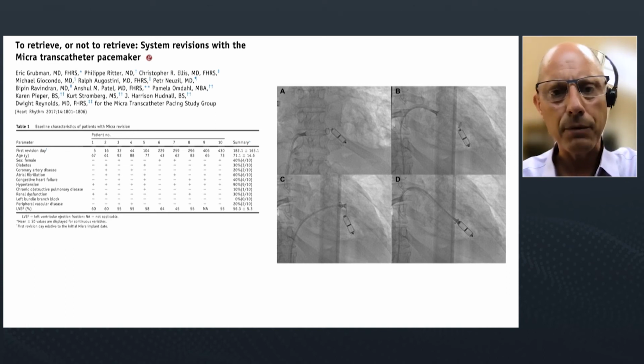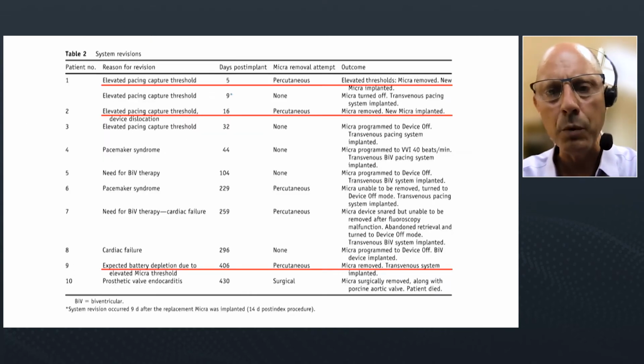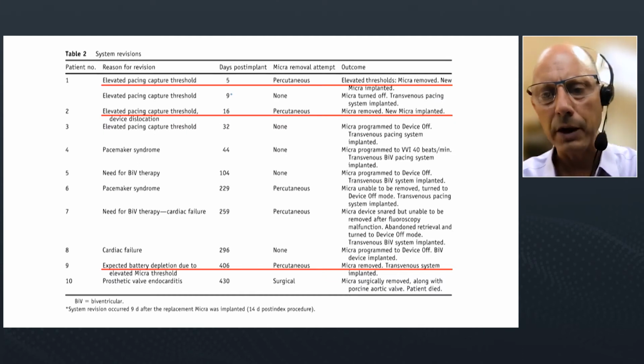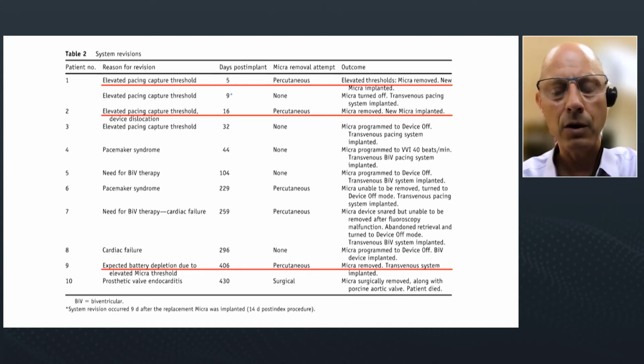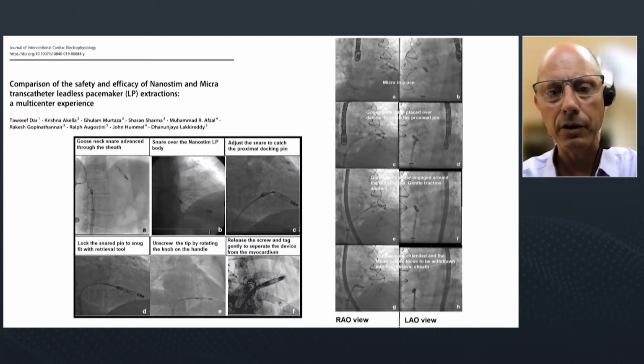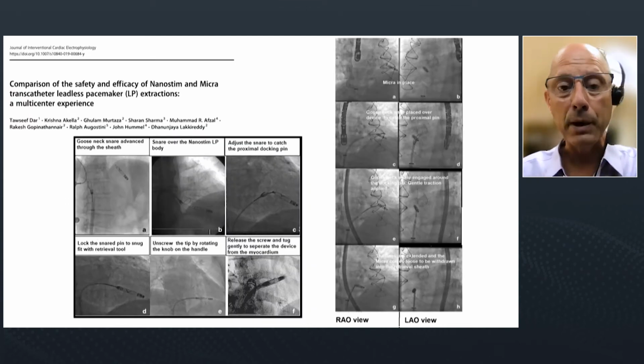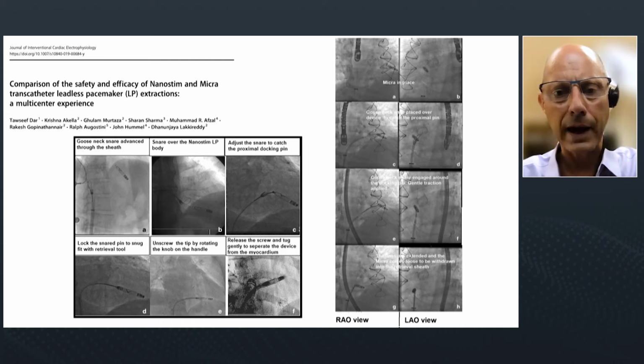And we can see here from the analysis of the Micra studies, 10 patients who required system revisions. What we can see from this is that there's various different strategies to this. In some situations, the device is attempted to be removed, but in many situations, because the device is very small, it's just programmed off, and then either another Micra device is implanted or a conventional transvenous device is implanted. And because of the problems with the Nanostim device and premature battery depletion, we do have quite a lot of experience of extraction of the Nanostim device.